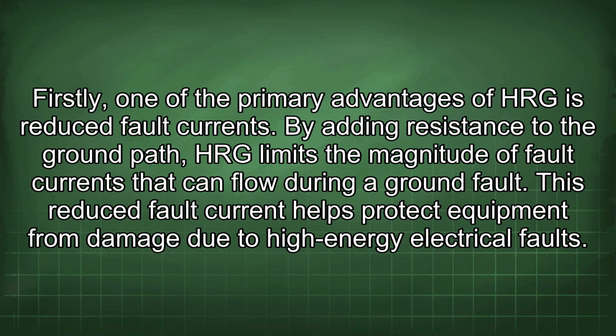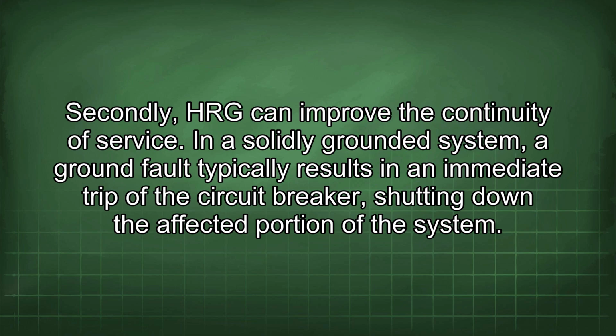By adding resistance to the ground path, HRG limits the magnitude of fault currents that can flow during a ground fault. This reduced fault current helps protect equipment from damage due to high-energy electrical faults. Secondly, HRG can improve the continuity of service. In a solidly grounded system, a ground fault typically results in an immediate trip of the circuit breaker, shutting down the affected portion of the system.